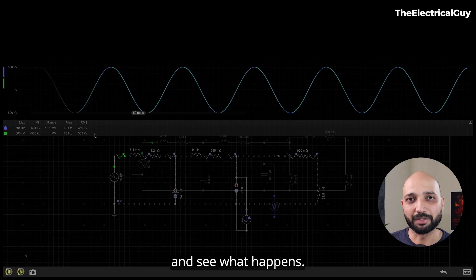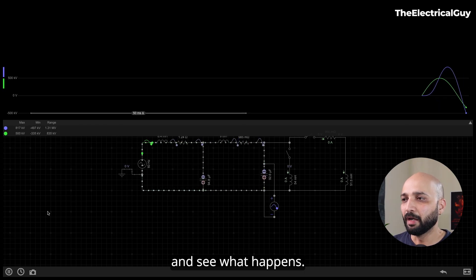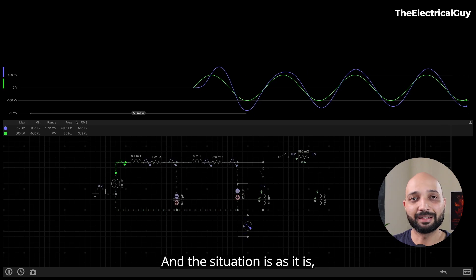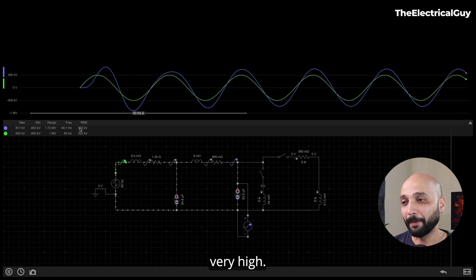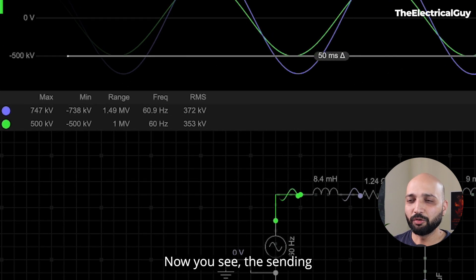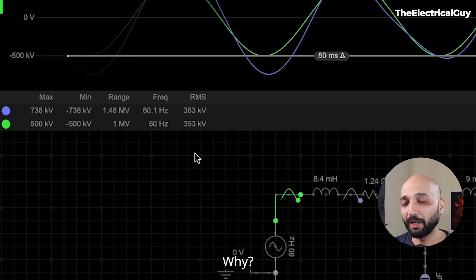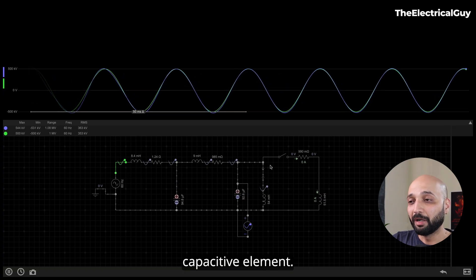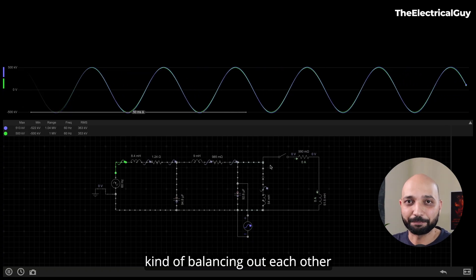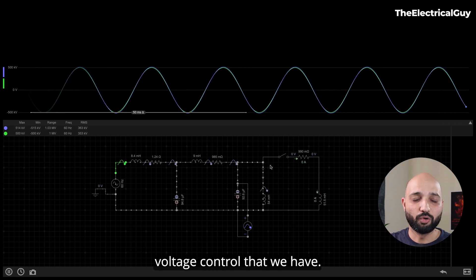Let's add the reactor and see what happens. Currently the transmission line is lightly loaded without the reactor, and the receiving end voltage is very high. Now we add the shunt reactor — you can see the sending end voltage and the receiving end voltage become equal. Initially there was only the capacitive element; now we have added the reactor as well, so they are balancing each other out. That is the solution to the voltage regulation problem.